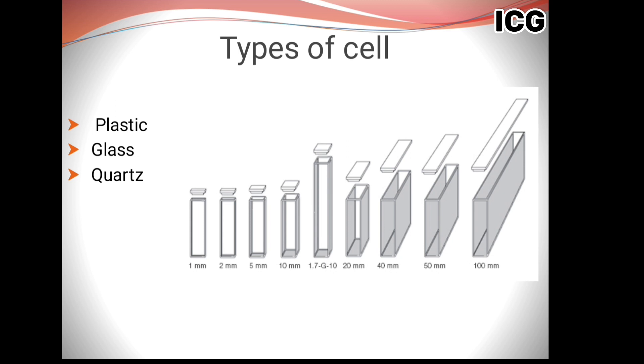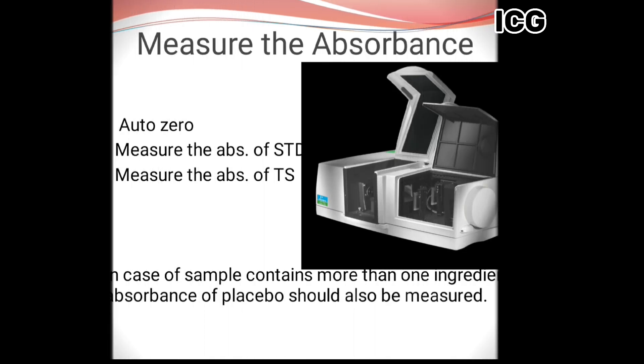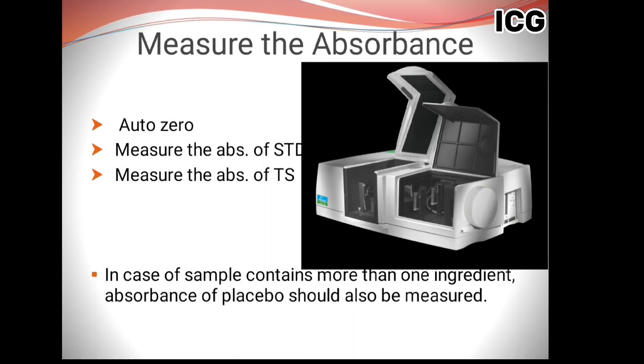For the final handling on the instrument — when you measure absorbance of the solutions you have prepared — first you will blank against the solvent in which you made the dilution. After blanking, the second step is to check the absorbance of your standard, and last, you run your test solution and record its absorbance.